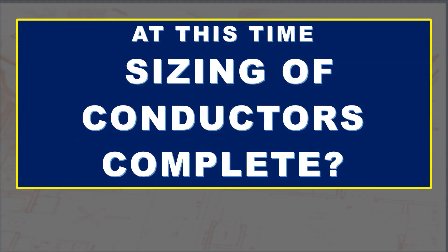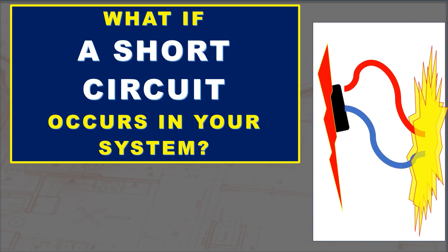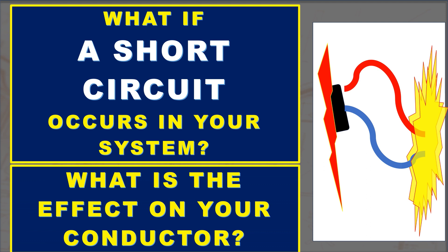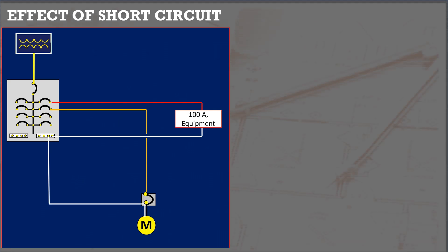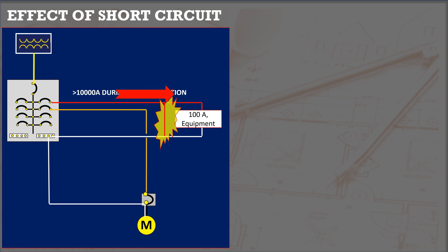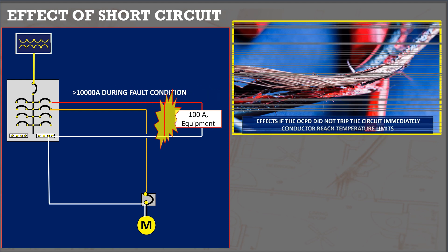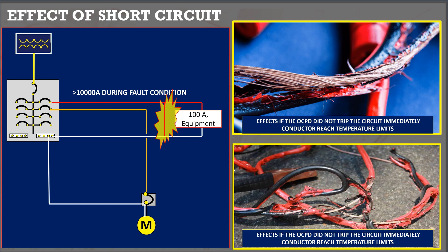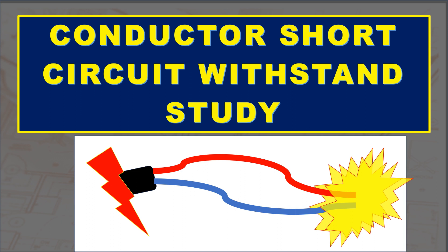At this time, is sizing of conductors complete? Almost. What if a short circuit occurs in your system? Since short circuit calculations are not part of the topic, I will show the effects if the overcurrent protective device does not trip immediately. During a short circuit, large amounts of current flow through the conductor. The heat generated depends on conductor size and material, as well as fault current and duration. The conductor has temperature limits depending on insulation material type. To avoid damage, conductor short circuit withstand study shall be included in sizing and selection.